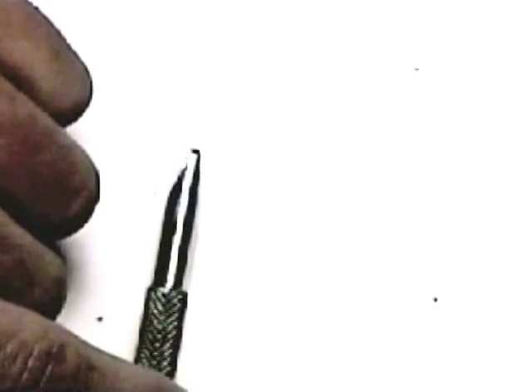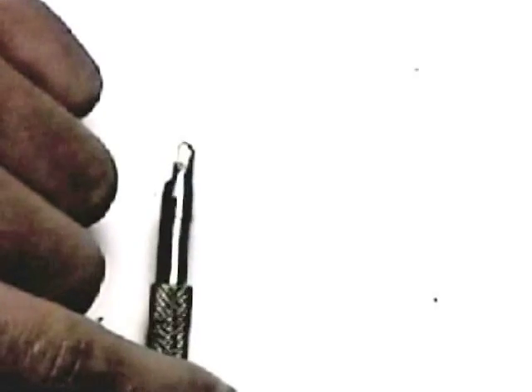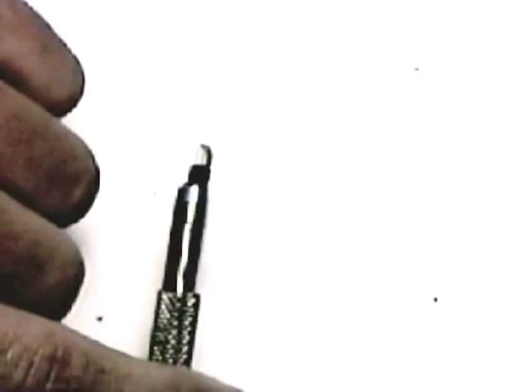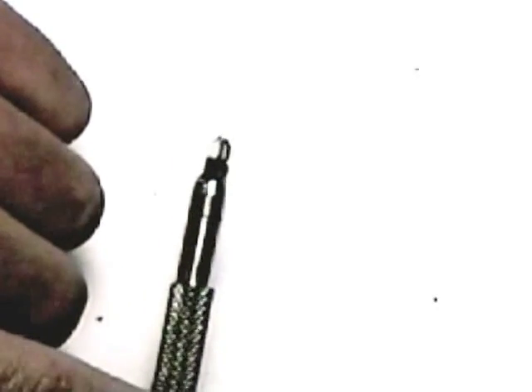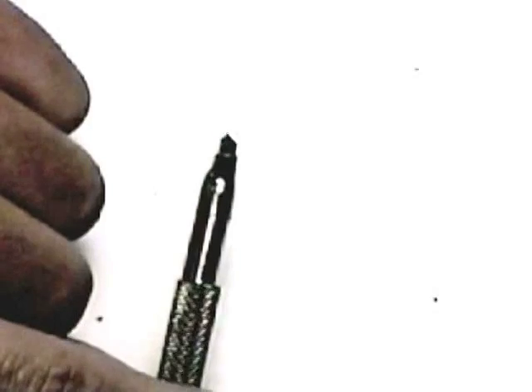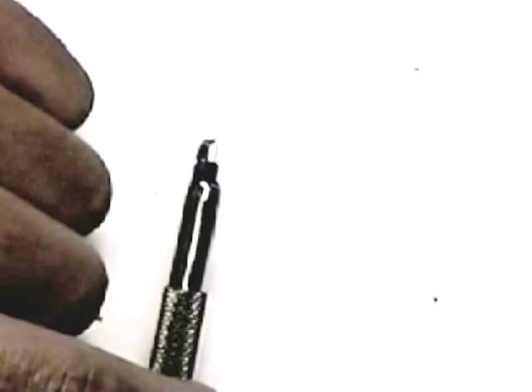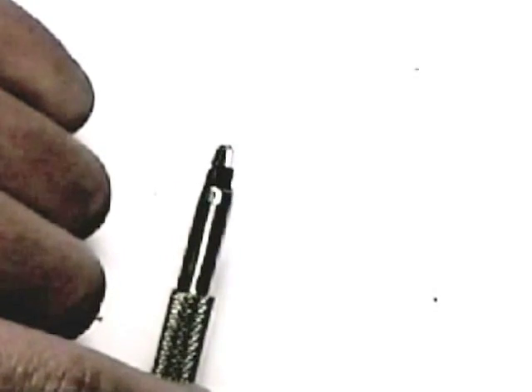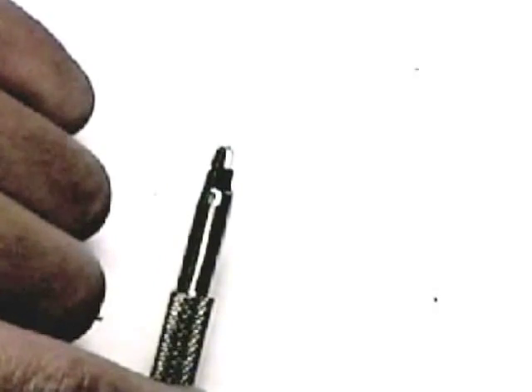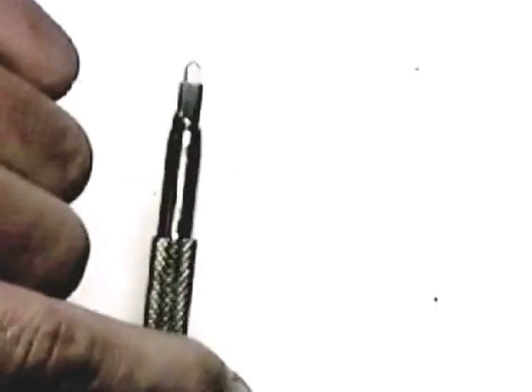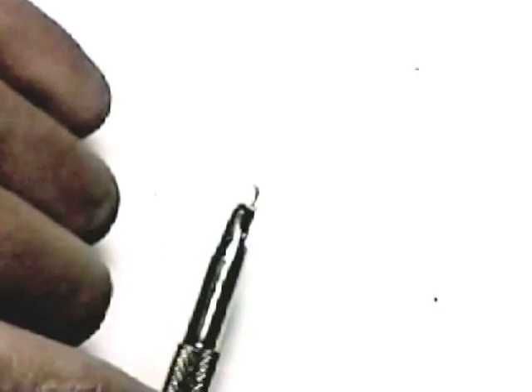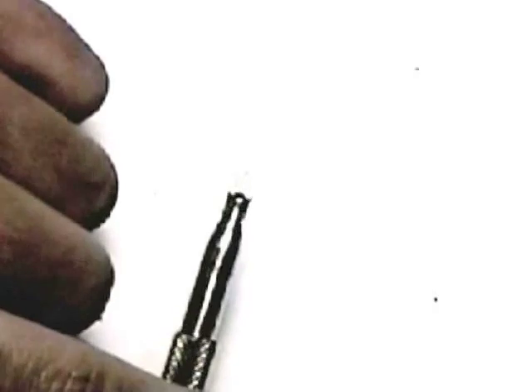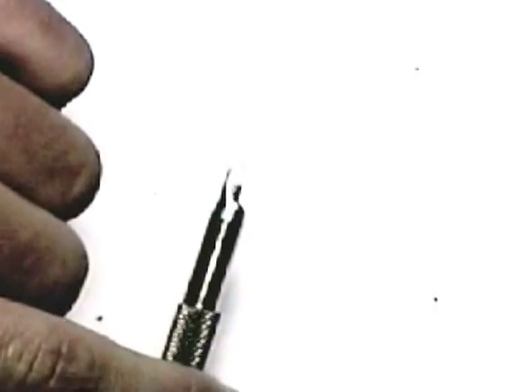Now the reason that this blade is available on this particular handle is so that surgeons can perform a groove step incision, which involves setting the blade at one of these calibrations, 300, 400, or 500 microns, creating a groove incision, and then setting the blade to full extension for entrance into the anterior chamber. Now there is one key regarding the usage of this blade in this handle configuration.